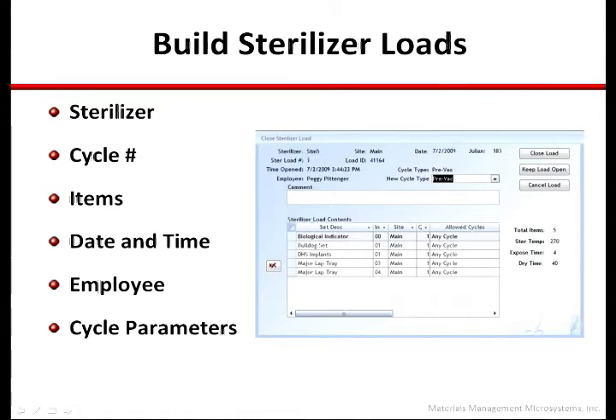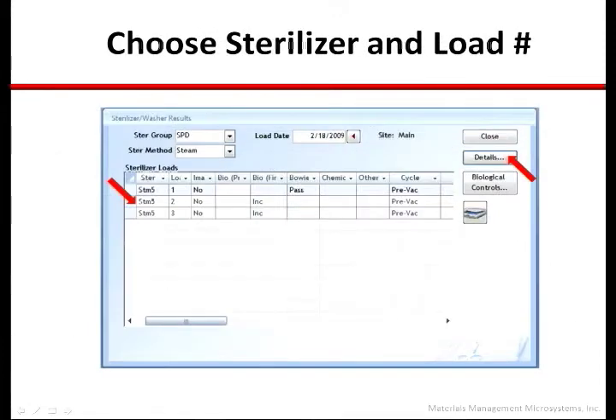When a sterilizer load is built, all of the items on the cart are scanned and their unique identification is preserved. The system will ensure items in the load are compatible with the type of sterilizer, will provide guidance on the selection of the cycle, and document the employee ID for increased accountability. The system will also prompt for the use of BI-PCDs based on the load contents and policies.